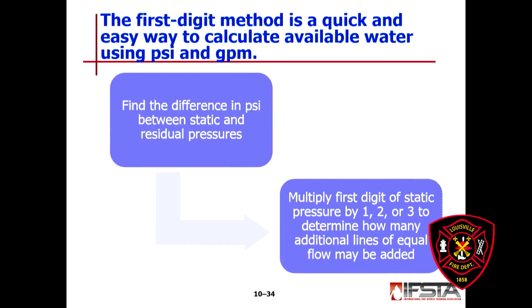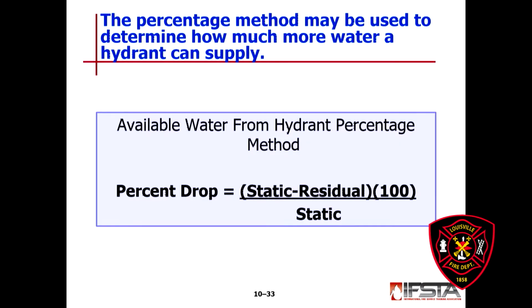So percentage decrease, let's back up here. Talking about the percentage method again - we do our calculation. 0 to 10%, as I said, 3 times the amount being delivered. So you can lay up to 3 more lines, say we already have 250 off, you can lay essentially 750 more GPMs worth of water. If you have a drop of 11 to 15%, it's 2 times; 16 to 25%, it's the same amount of water. Anything over 25%, you're pretty much tapped out.